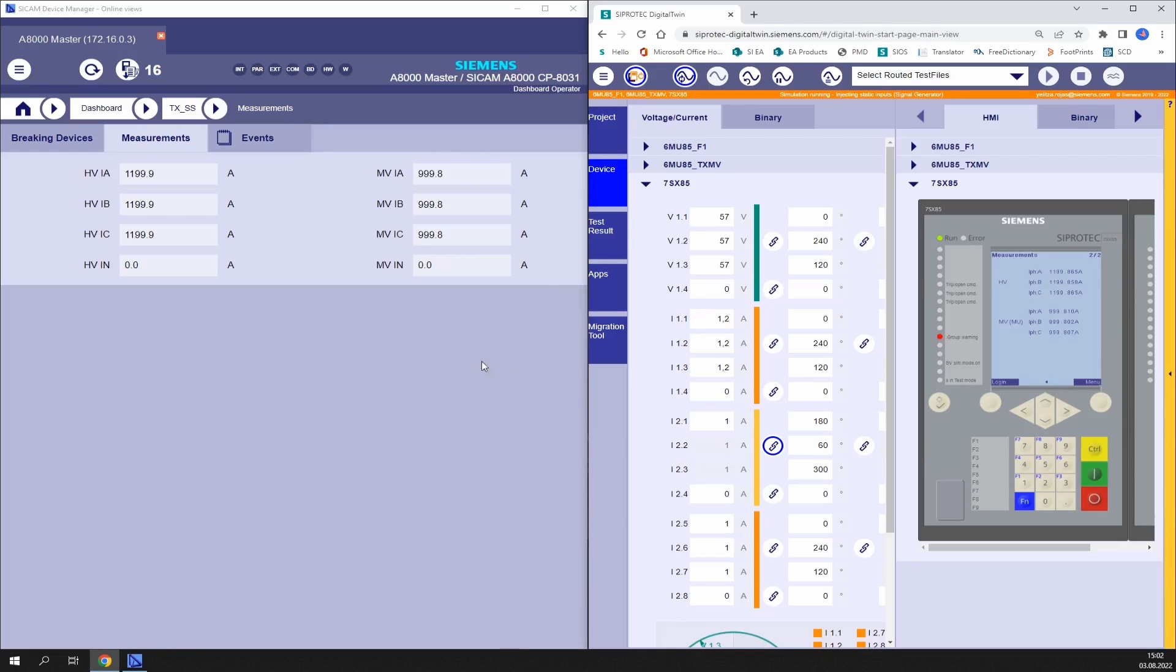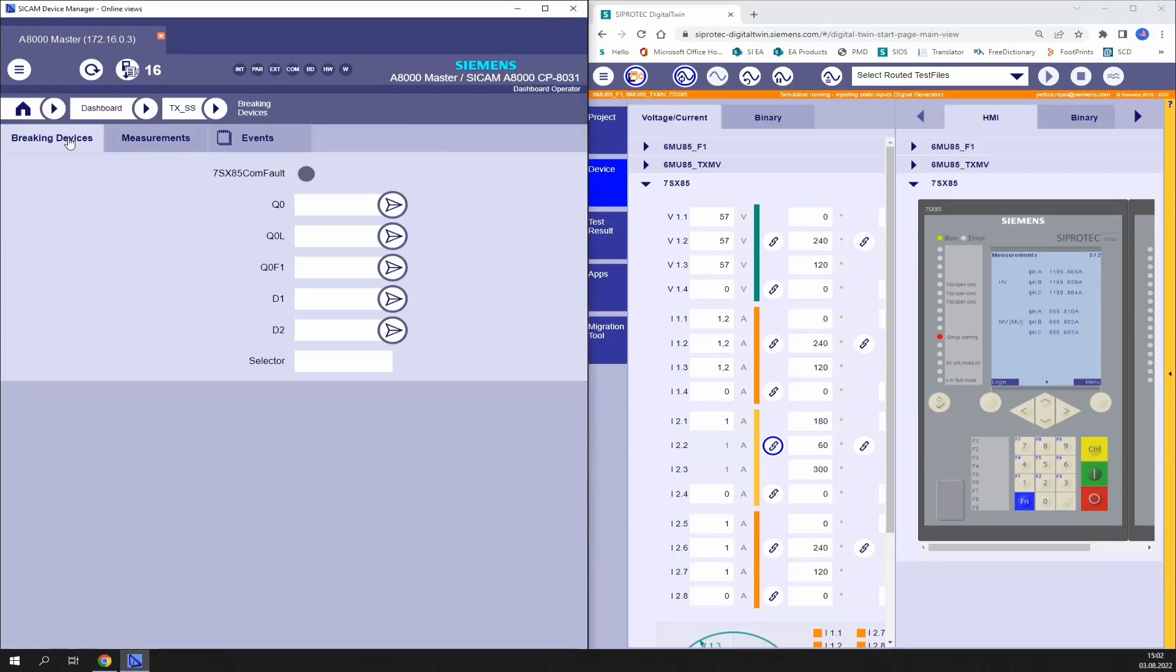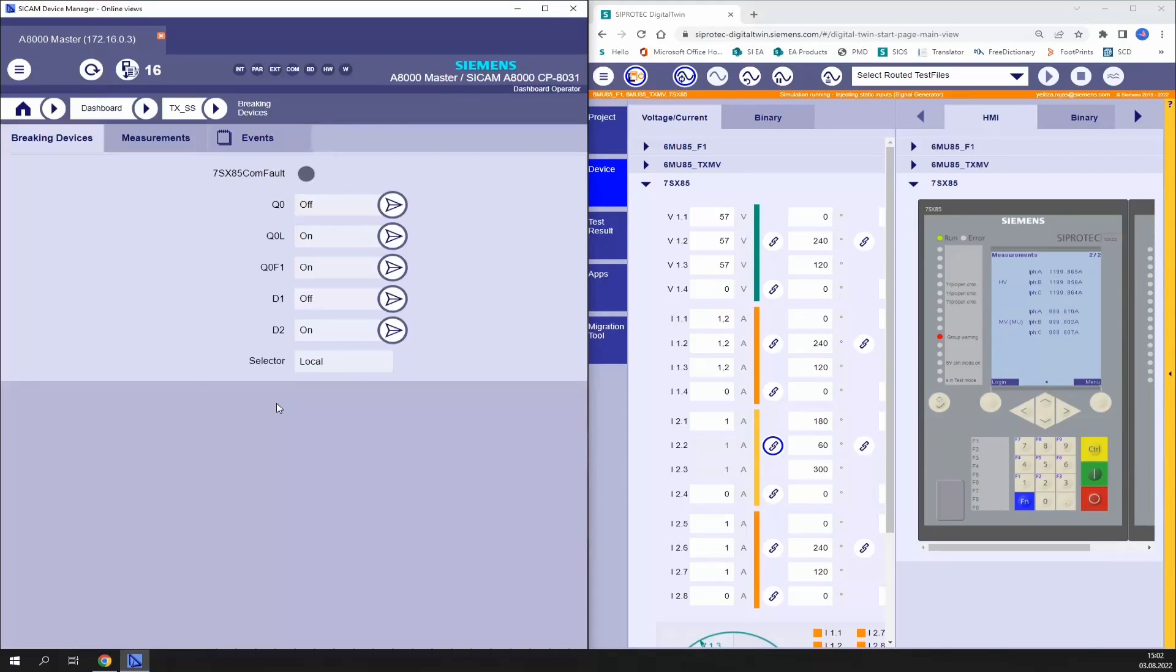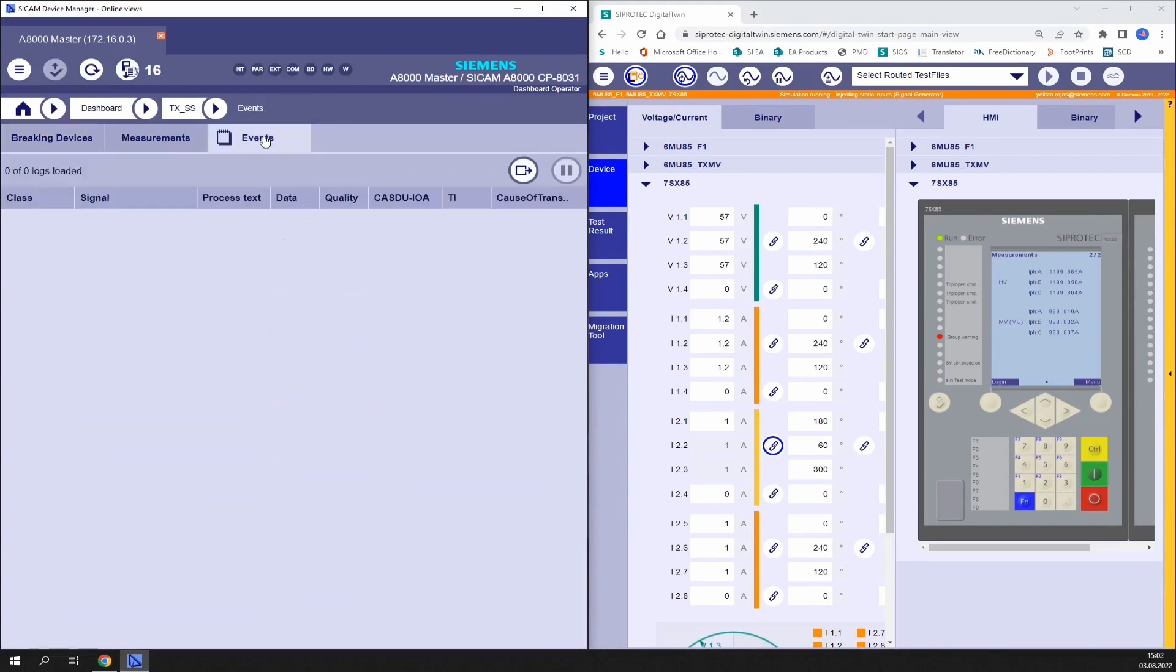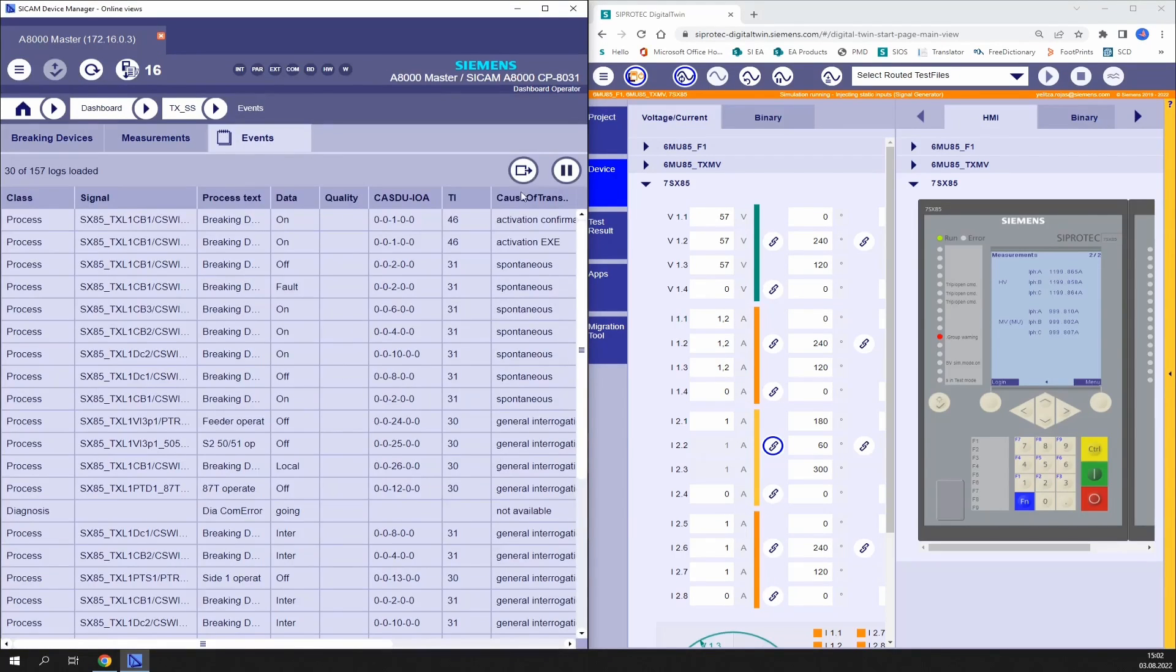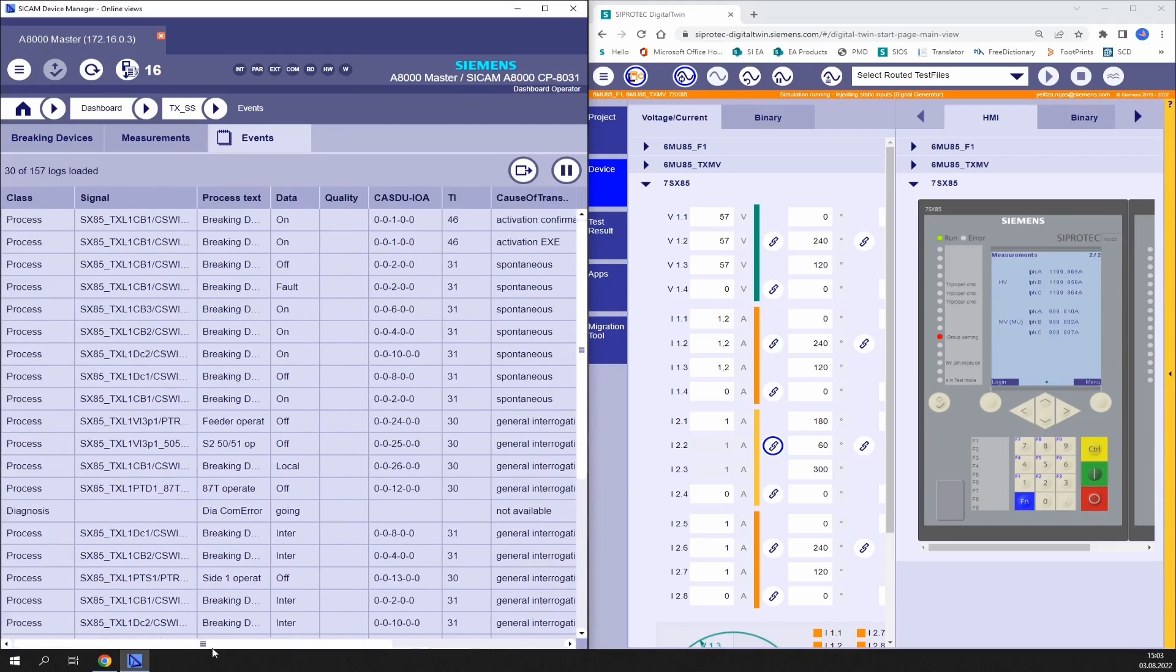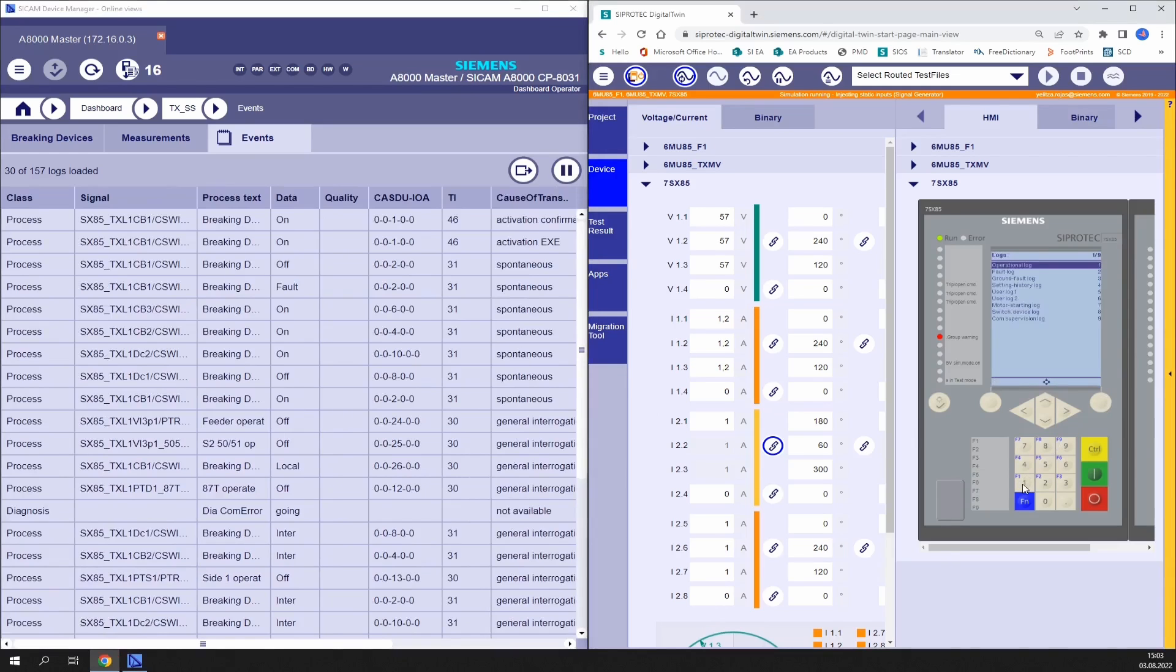As next we can test a control command. We can try to release a close command from the SICAM A8000 to the circuit breaker. But as you see here we have our selector in local which means that the order shouldn't proceed, but we try it any case. Checking the event list we find the information that the command was activated but the confirmation is negative. And if we check also in the logs of the protection device we see the same information.